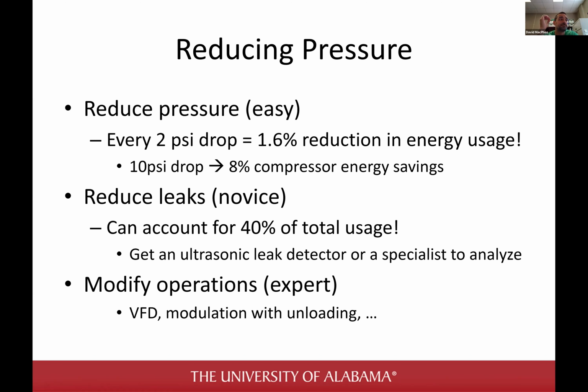As I said before, 80%-ish of the energy that goes into an air compressor goes away to waste heat. So if you're using compressed air to cool you off, that's 5 times more energy than you should be using for a fan. Okay, so just keep that in mind. But we have seen leaks be incredibly prevalent in some systems. If you want to diagnose leaks, you fix fittings, seals, all that stuff. You can do that with an ultrasonic leak detector or a specialist to analyze.